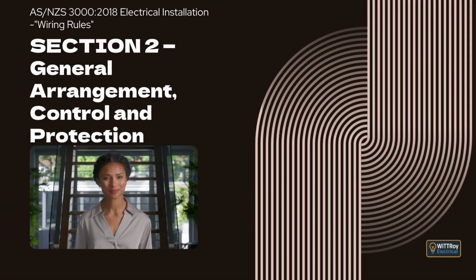Clause 2.5.5.3 Limitation of the harmful effects of a switchboard internal arcing fault. If a fault does occur, this clause explains how to limit the damage. A protective device must be installed that will disconnect the arc as quickly as possible. The arcing fault current is normally assumed to be between 30% and 60% of the prospective short-circuit current. To keep the switchboard safe, the protective device must operate at a current below 30% of the prospective short-circuit level.